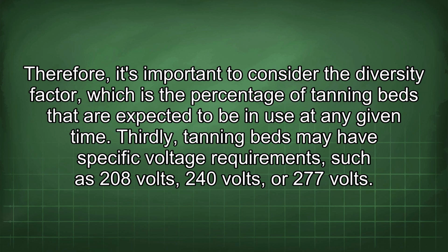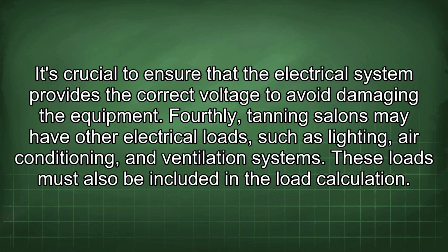Therefore, it's important to consider the diversity factor, which is the percentage of tanning beds that are expected to be in use at any given time. Thirdly, tanning beds may have specific voltage requirements, such as 208 volts, 240 volts, or 277 volts. It's crucial to ensure that the electrical system provides the correct voltage to avoid damaging the equipment. Fourthly, tanning salons may have other electrical loads, such as lighting, air conditioning, and ventilation systems. These loads must also be included in the load calculation.